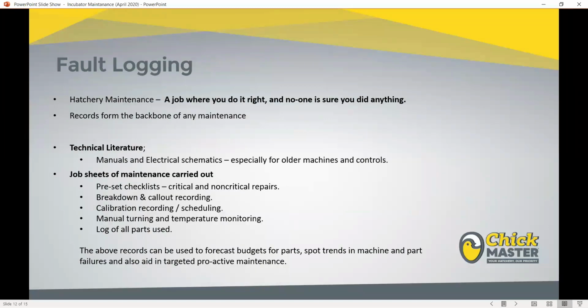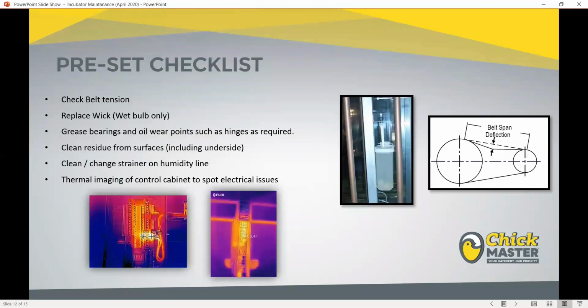Craig, before you move on, let me just pick up one or two questions. As you're doing a preset checklist there and you're talking about belt tension, how do you know when you have a good belt tension? The easy way to tell is twanging it with your finger. So if the belt slips when you first start a machine up, it's not tight enough. And if your pulley or your main fan frame is deflected, so the alignment is not entirely plumb, so it's not perfectly vertical, then it's too tight. The sweet spot is somewhere in the middle of that.